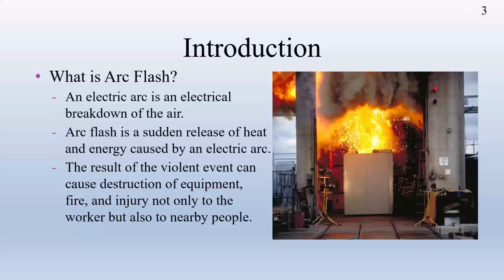And this will be a sudden release of heat. If you have ever experienced it, I hope not, it is going to create a big bump, and it is such a sudden release of energy. That can cause an injury or even be fatal to a worker nearby. When you talk about a short circuit, since R equals 0, there is no energy release. But in an arc there is a resistance between the two conductors, so I squared R produces the energy that can release millions of joules in one incident.